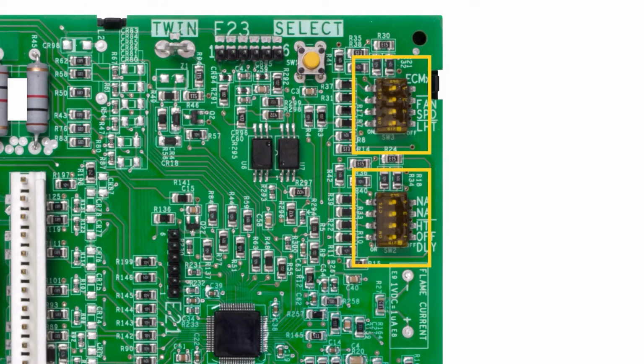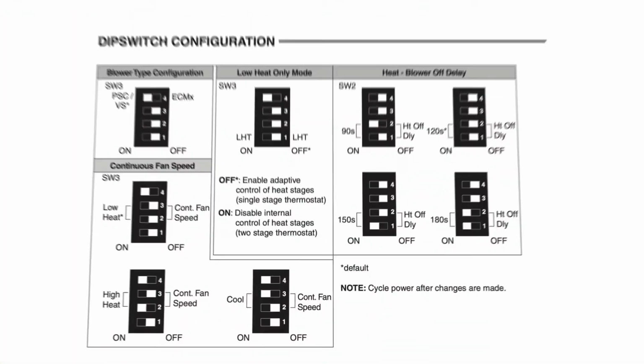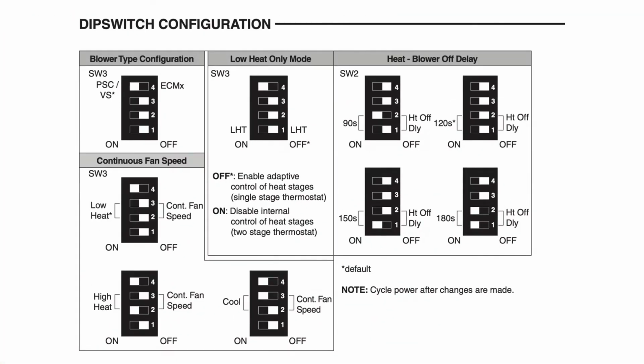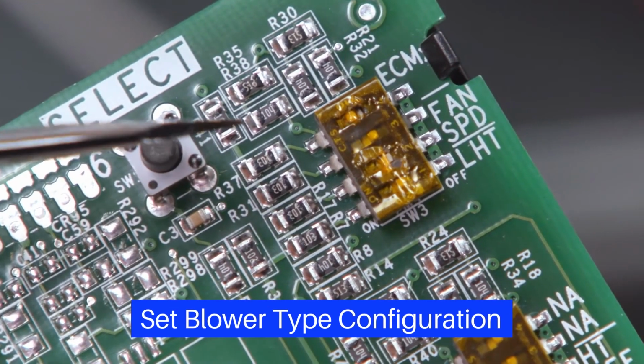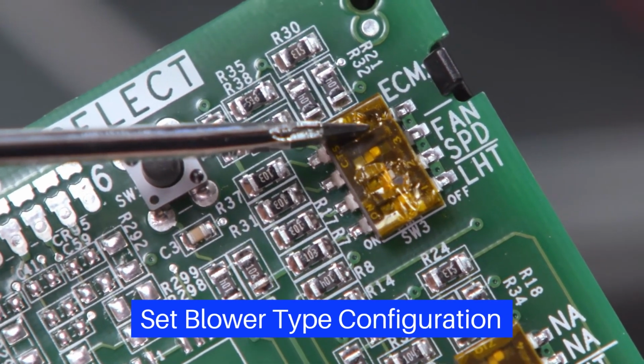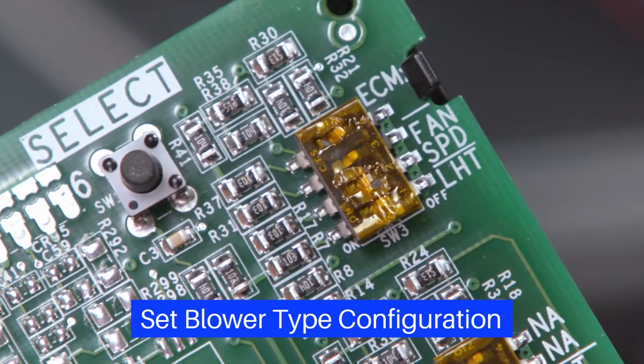Dip switch settings should match the existing control. Make adjustments according to the dip switch configuration chart in the instruction sheet. The default blower type configuration dip switch is set for PSC and variable speed blower motors. For this application with an ECMx blower motor, SW3 dip switch number 4 can be moved to the off position by breaking through the yellow plastic film.